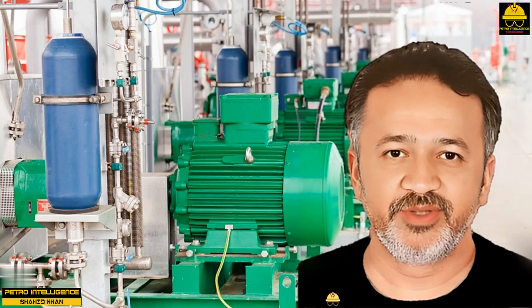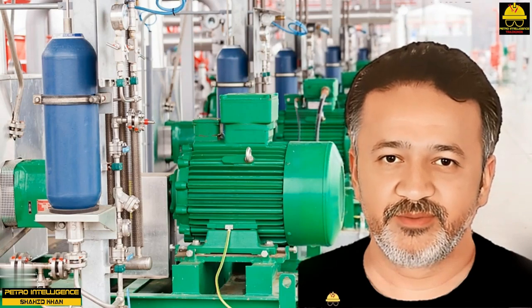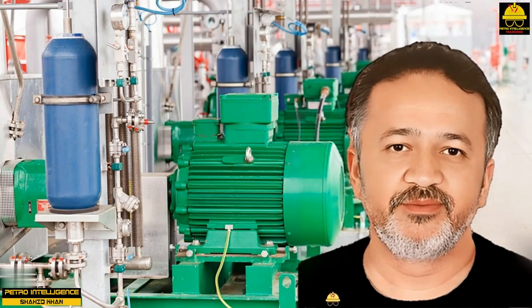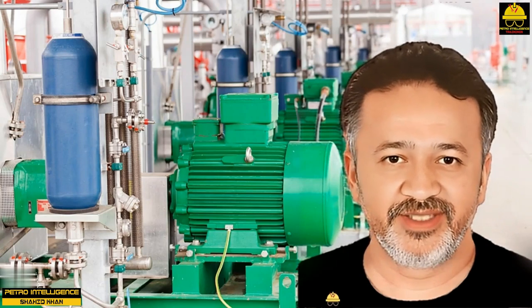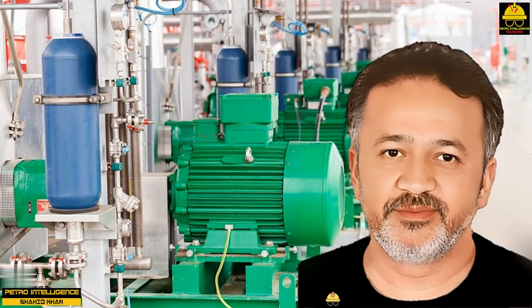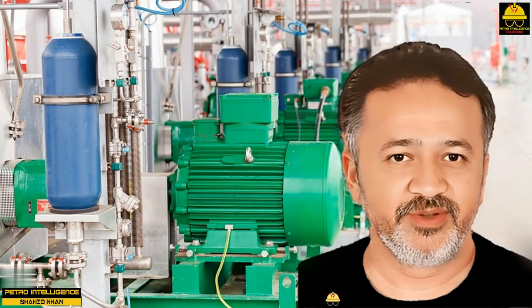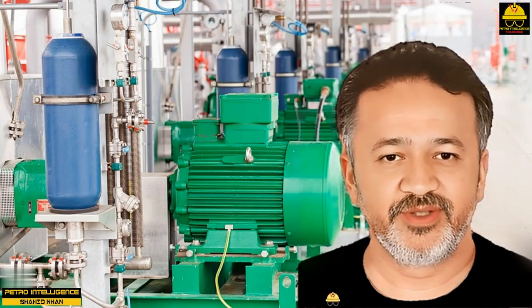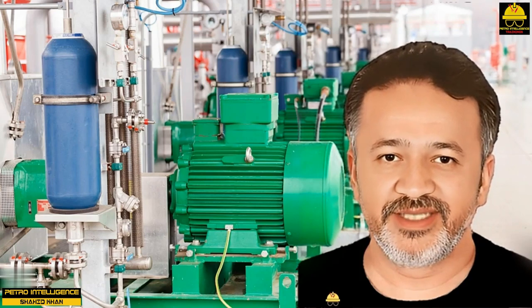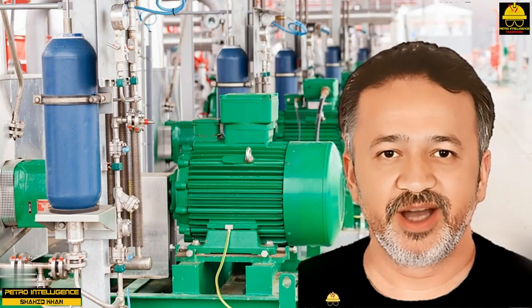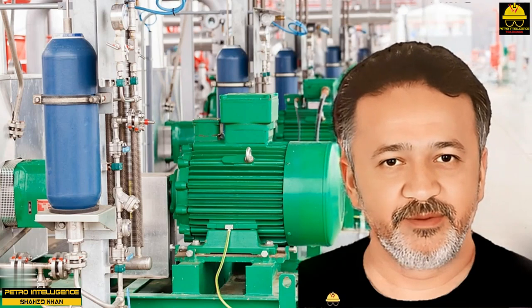When a designer builds a multi-stage pump, the concept of thrust must be considered. The suction side of an impeller exerts a small force on the shaft. The discharge of the impeller exerts a significant amount of thrust on the rotor. Collectively, the sum of the forces along the shaft is tremendous in a multi-stage pump.